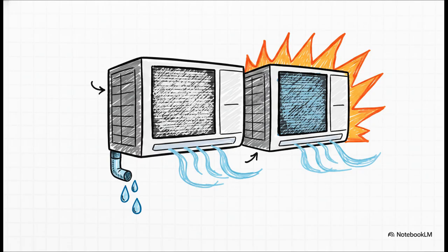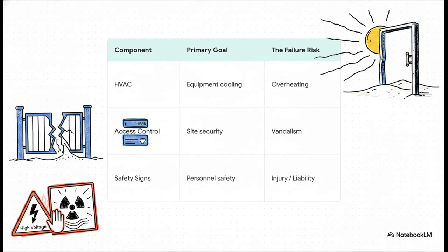Telecom equipment generates a massive amount of heat, and ignoring filter hygiene just forces the compressor to work twice as hard until it burns out. Also, professional sites use a lead-lag cooling redundancy. Basically, if the primary lead unit fails, the backup lag unit must automatically take over. If it doesn't, the equipment will start throttling its performance and eventually shut down completely just to avoid melting. Failing to secure warped doors from the desert heat or ignoring radiation safety signs transforms a perfectly reliable site into a massive liability.